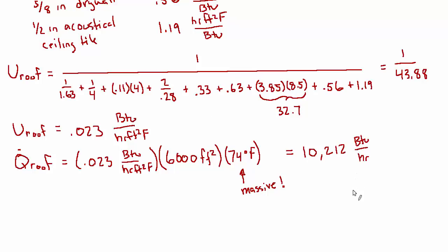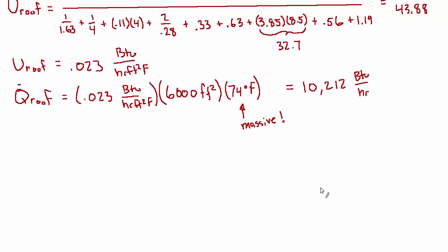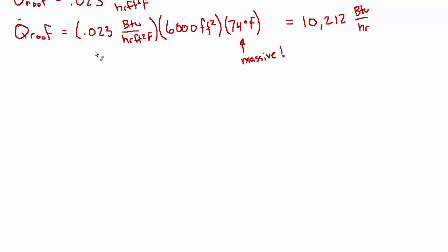So that gives us 10,212 BTU per hour. And that's in addition to what we already computed for the walls. So we've done the walls, we've done the roof, and now we're ready to look at the windows. And this is where it gets a little confusing. So when it comes to solar load through windows, the section I always flip to is 43.9.